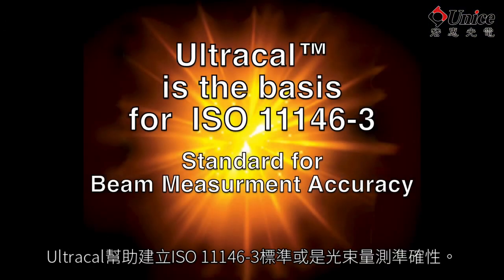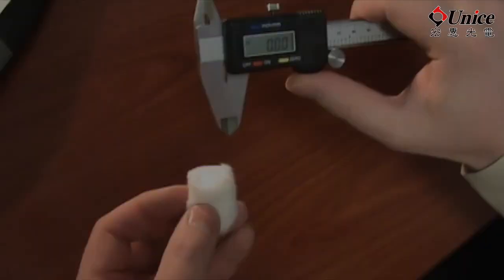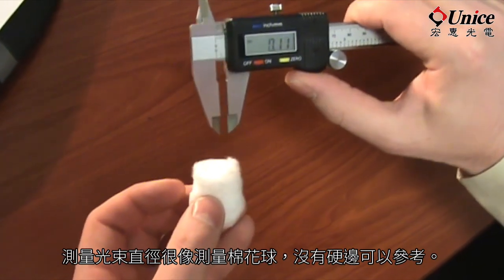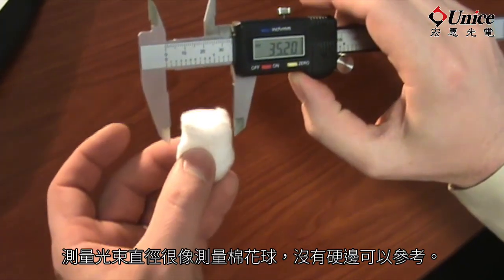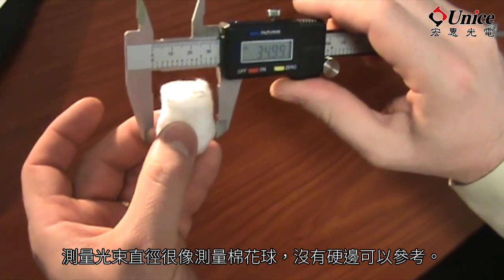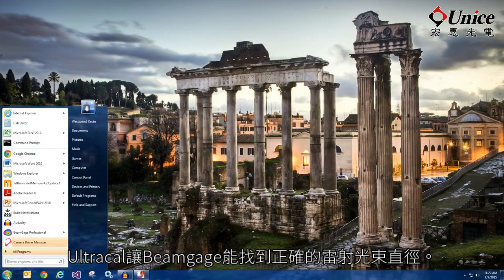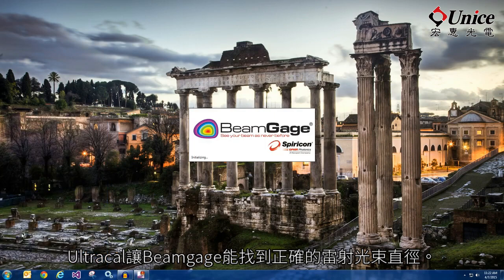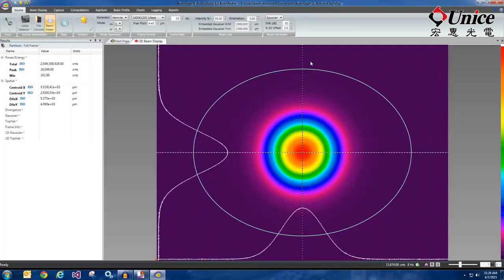Ultracal helped establish the ISO 11146-3 standard for beam measurement accuracy. Making a beam diameter measurement is a lot like measuring a cotton ball. There is no hard edge to reference. Ultracal enables BeamGage to find the true beam diameter of the laser beam.